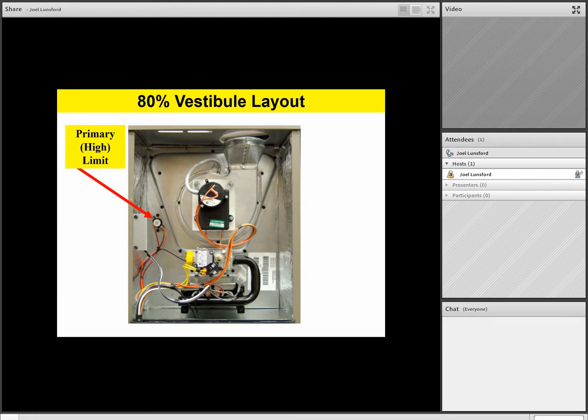limit. Now please note that this high temperature limit is an automatic reset. And the main cause for that high temperature limit to open or to be cycling is poor airflow. Poor airflow is the #1 cause. So want to make sure that if you have a 4 flash code indicating a high temperature limit is opening up, that the #1 thing a technician should check is the air filter. And then of course fan speed and duct work and so on go hand in hand with that as well. But the #1 cause for a high temperature limit to open is inadequate airflow.